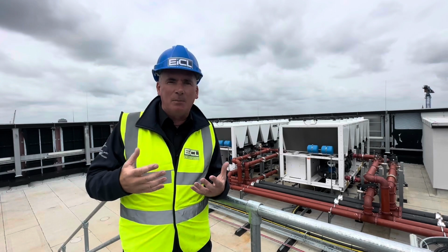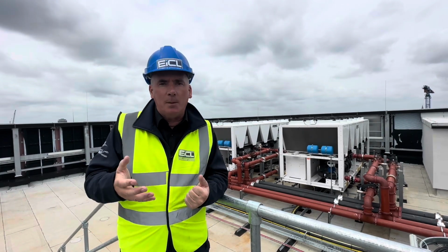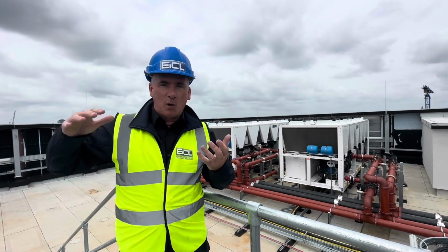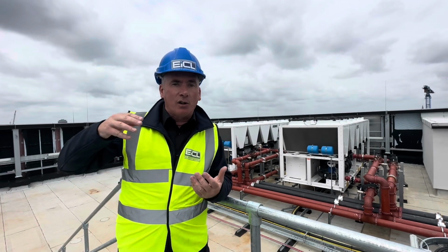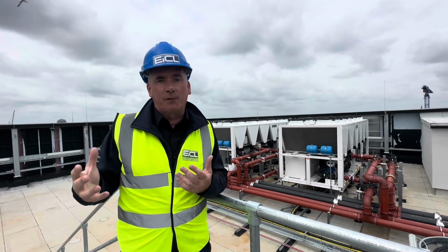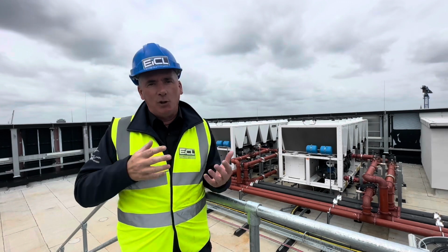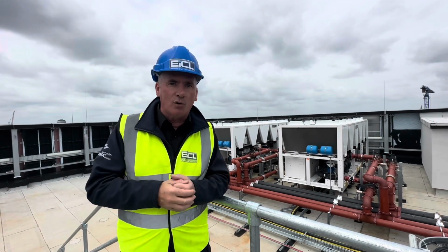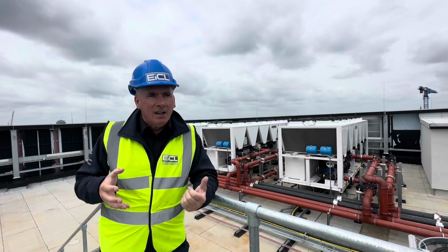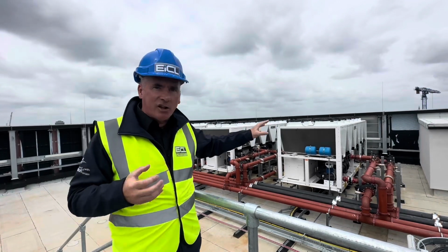We can do the exact same with chillers or multifunctional heat pumps, or even heat pumps for that matter. So as the temperature comes up, we don't necessarily need your water temperature to be high. You can drop that, and vice versa with the cooling. As the temperature drops, you can adjust it as per the load or as per the ambient. So you can see the installation here brings it all to life.